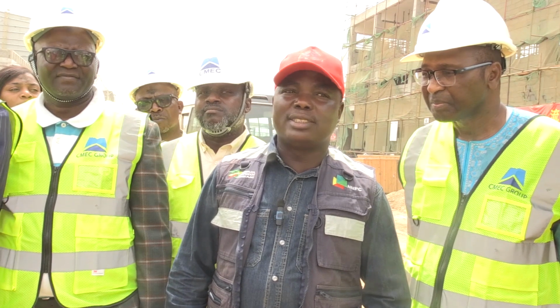Already we have another project coming under AFD, that is the Luke Bay. The bay for Luke Bay to be 330 is already there at Gwagwalada. So as soon as that bay is connected - because Luke Bay is also coming up - we are very sure of the evacuation as a dia state, because already there the capacity we have is 2 by 150 MVA. So the additional 350 they are talking about, already we have 2 transformers that will evacuate that energy at Abuja.